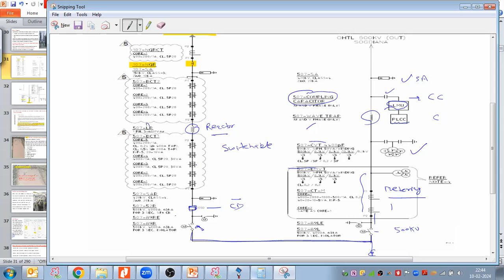The circuit breaker must have this controlled switching device. I will take up this controlled switching device in the breaker topic. What is a controlled switching device? CSD. When it is required, when it is not required. When I require precise switching for a dedicated circuit, at that time, along with the breaker, we use some devices. So this is one device, the controlled switching device. I will take this point with the breaker modules, CSD, so that I can get the point on wave switching, which CSD will provide.